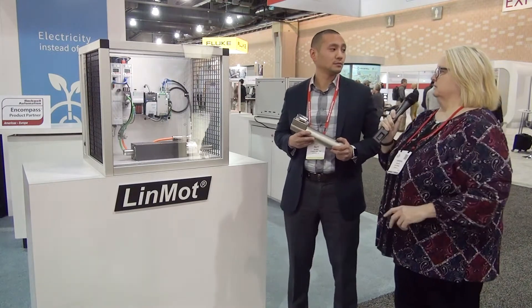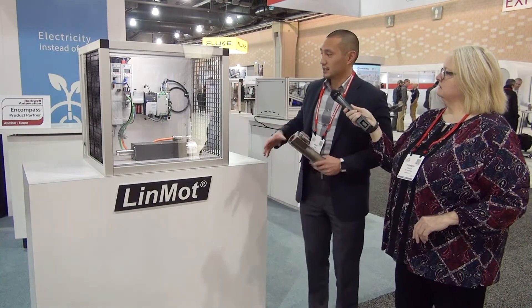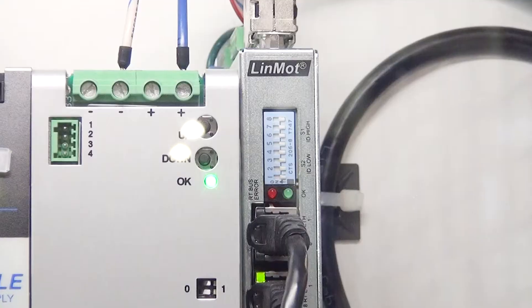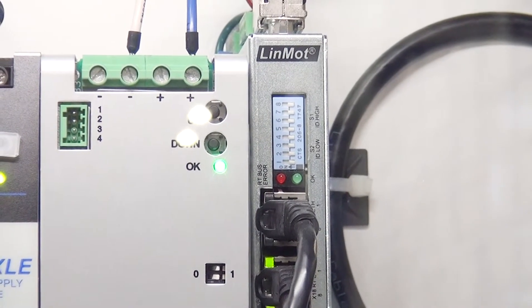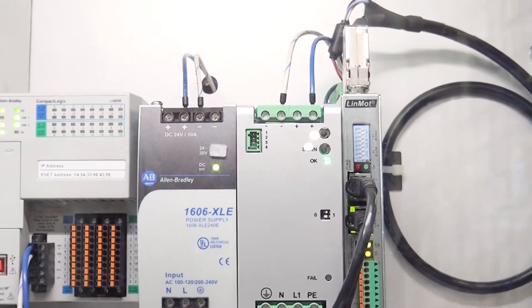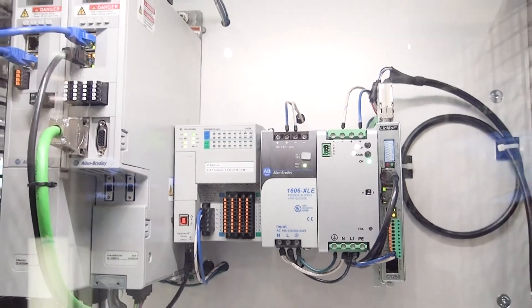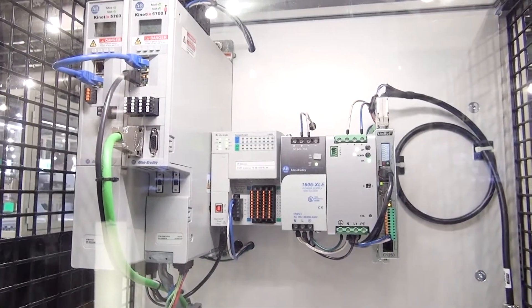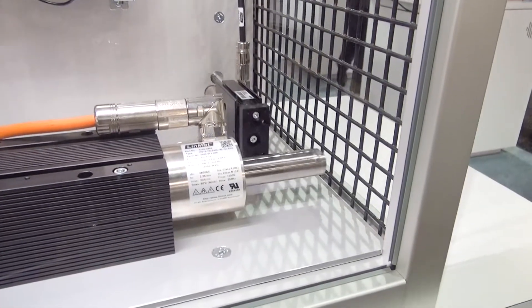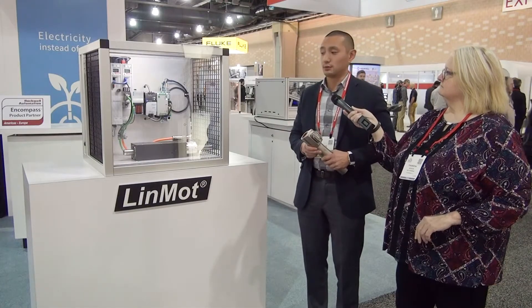One of the great things we have is our integration into the integrated architecture of Rockwell Automation. What we're showcasing here at the show is one of our new products, the C1250 EtherNet/IP drive, which now has the functionality of CIP Sync — so we're able to do time-stamped coordinated motion utilizing the CompactLogix and ControlLogix motion processors. We're also showing the integration with the Kinetix drives. Our three-phase motors have the ability to be in the native motor database, which helps with commissioning of your machines.